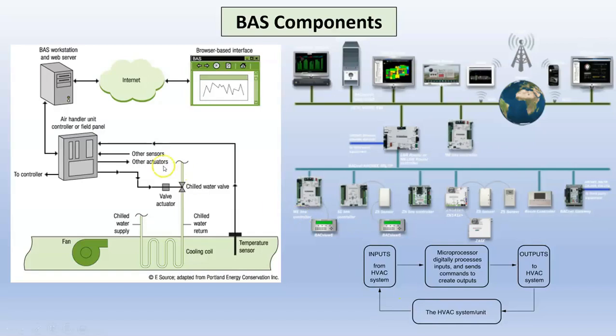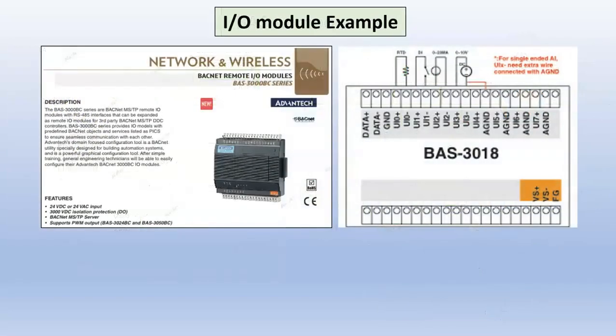Now, one of the beauties of this, if you see here between the I/O module and the controller, you're just going to have one little data cable here. Well, back in the day before you had a BAS or an EMS, every one of these devices would be hardwired all the way back to the controller, or to whatever was controlling the device, the thermostat. So you've eliminated a ton of wire by taking these multiple field devices into one I/O module and then having a data cable run. Here's an example of an I/O module, what they look like.